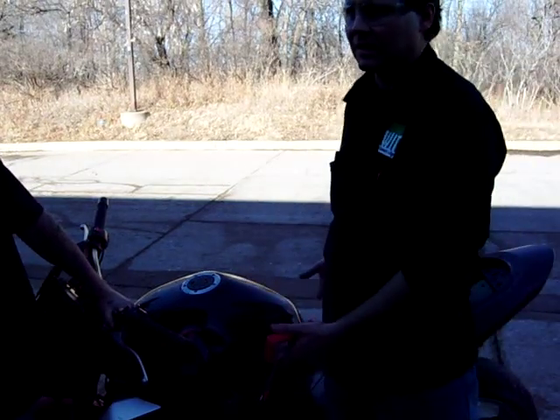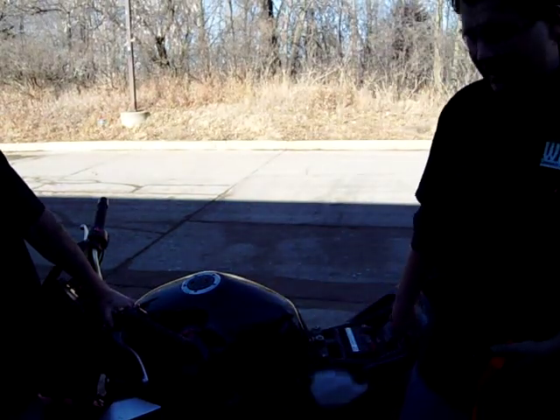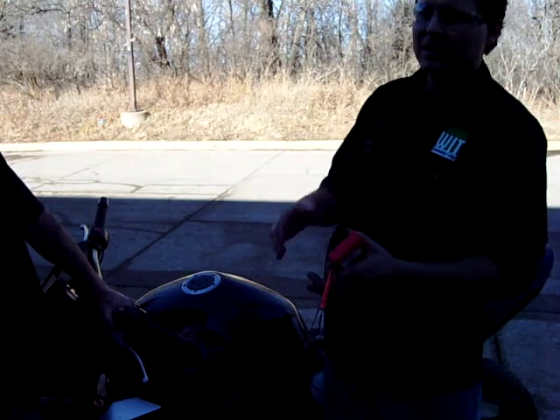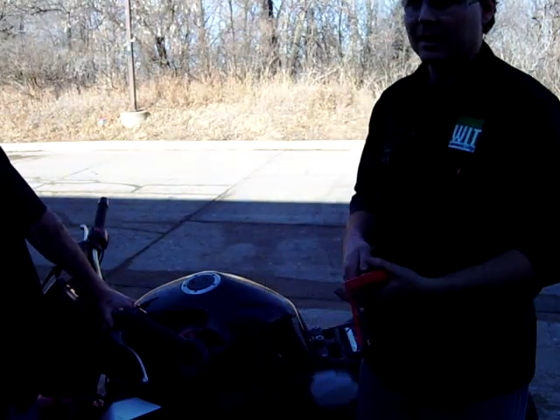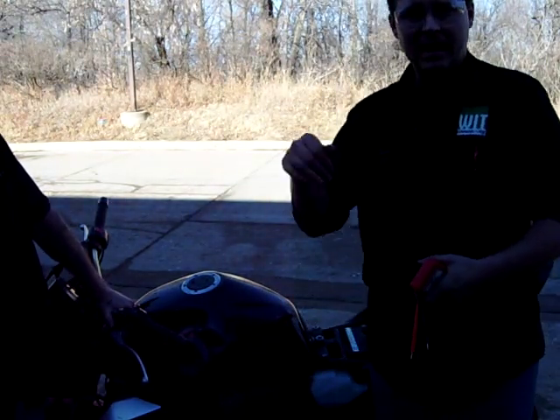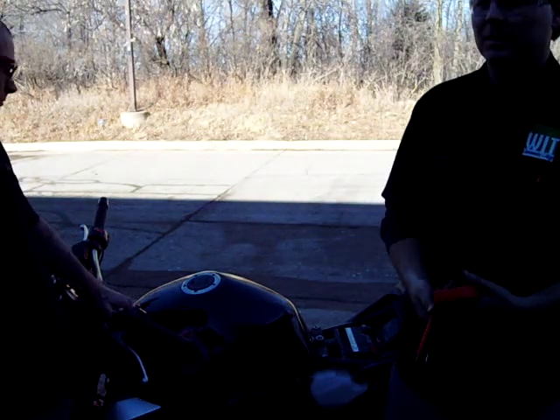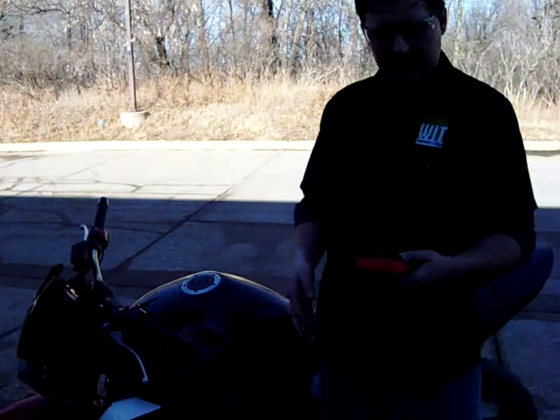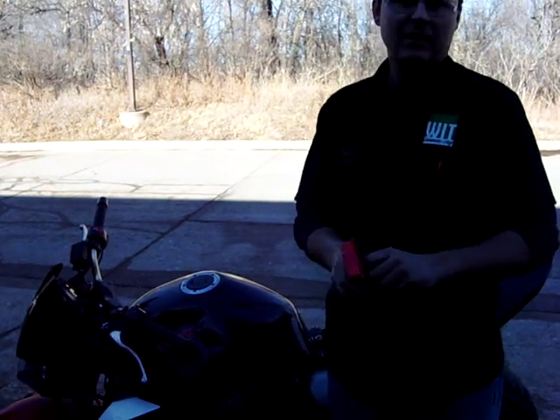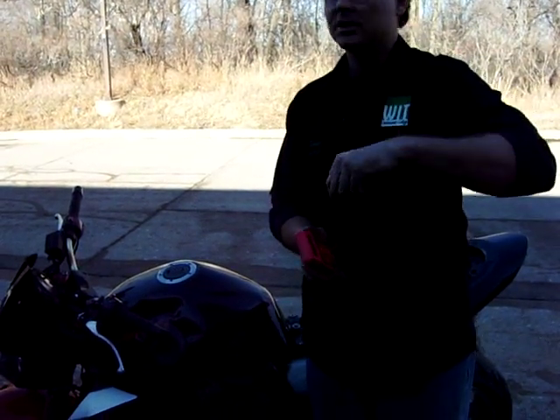It's simply because that regulator's not doing its job. Other than the fact that if we had a bad ground on the regulator, not allowing it to dump, we've got a problem going on there. Anyway, that's everything we've got going on so far for your three-phase permanent magnet charging system.